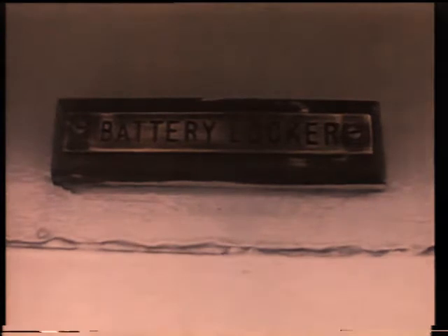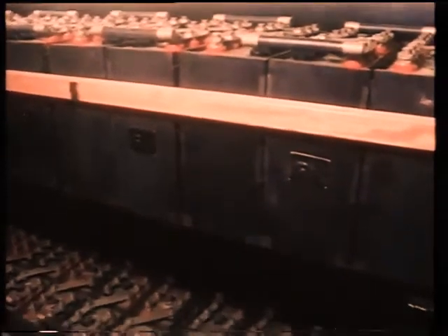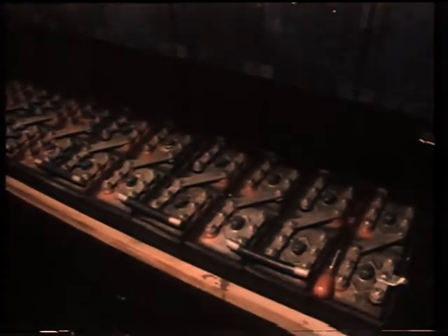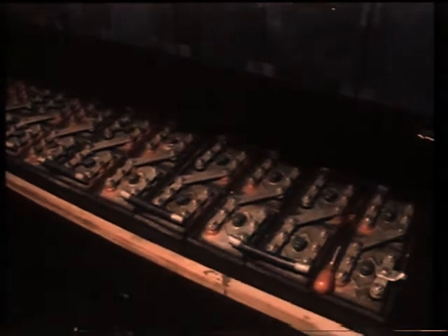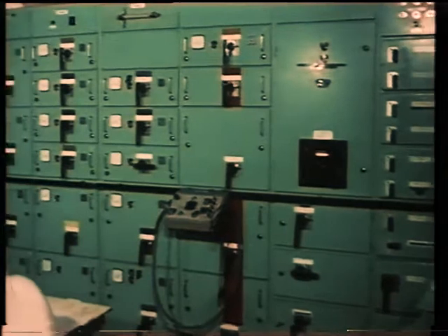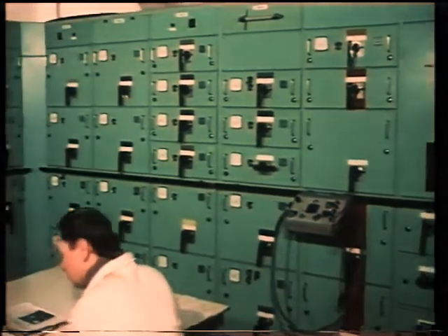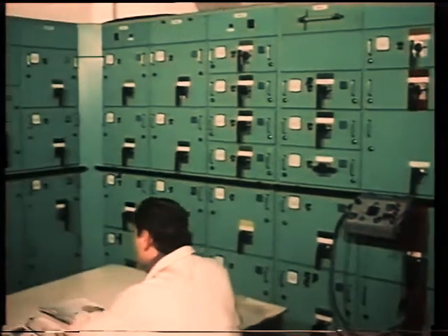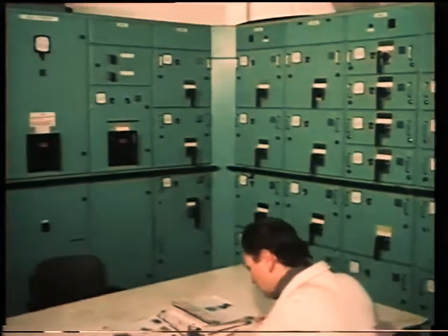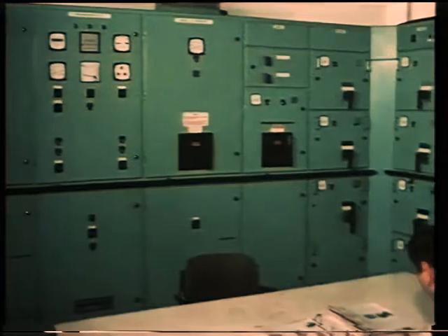In addition to this, a minimum level of lighting, fire, and general alarms and communication systems must be supplied by a battery supply during an emergency, when the main supply is interrupted for any reason. The heart of a ship's electrical distribution system is the main switchboard. The generated power is connected to it by the alternator circuit breakers, which connect power to the bus bars.